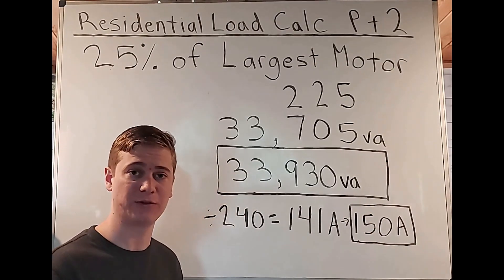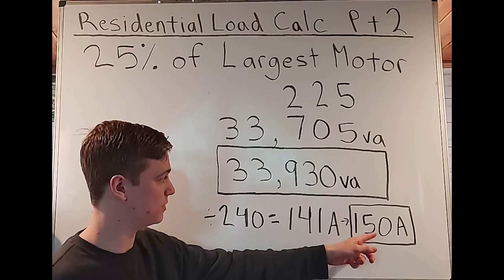If that next size is not exceeding 800 amps and you can just flip a page back to remind yourself of this. If you can't quite remember, 800 amps, it's right there, the page before it. So that's how I know that now we're sizing this up to 150 amps for our circuit breaker. And now with this, we can figure out what size conductors we're going to use with that circuit breaker.